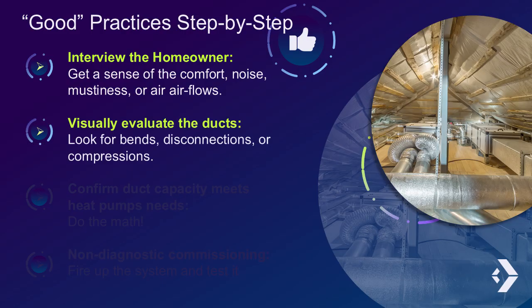Next, visually inspect accessible ducts. Look for bends, compressions, disconnections, discolorization of insulation, joist panning, which is very leaky, and awkward restrictions to cross-sectional areas, like riser chases between floors. You might also notice oddities like grills or registers being taped shut or blocked by furniture. Pay close attention to anything that might be causing the homeowner discomfort.